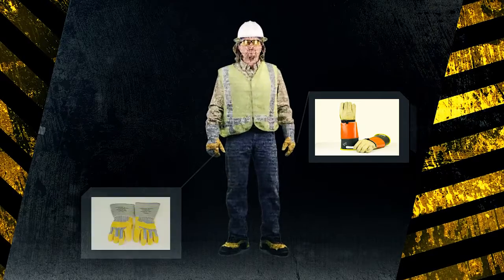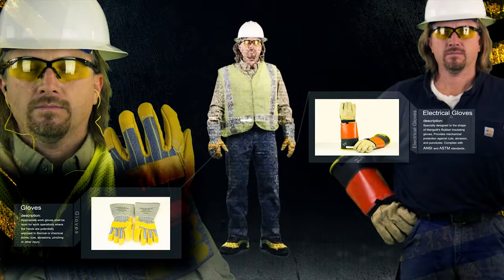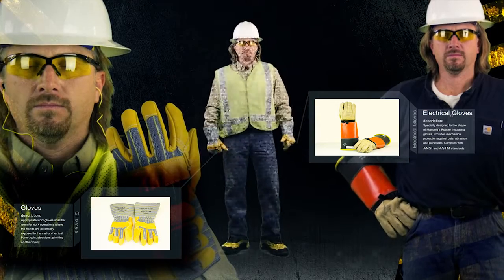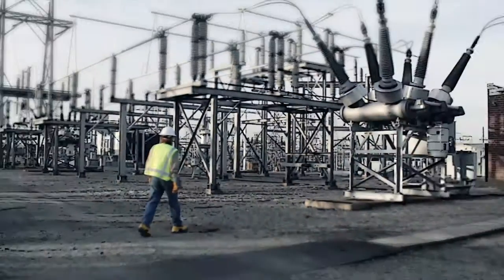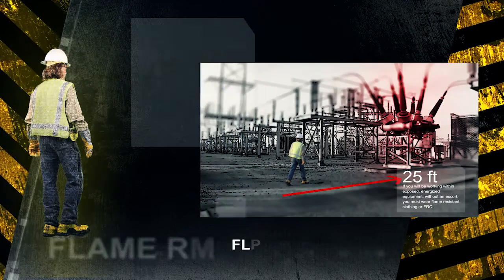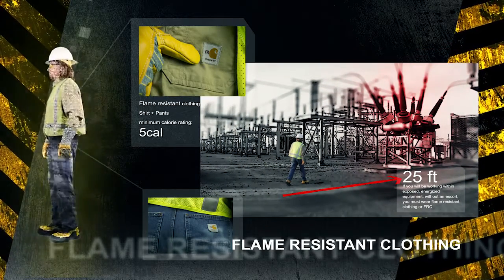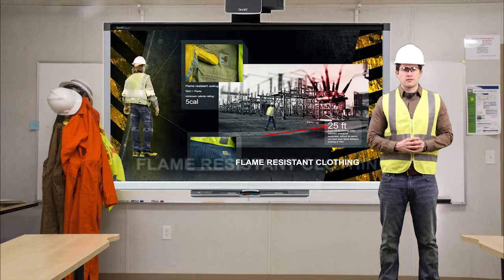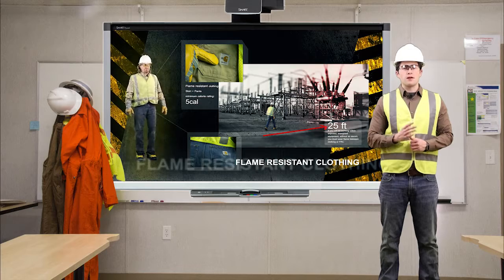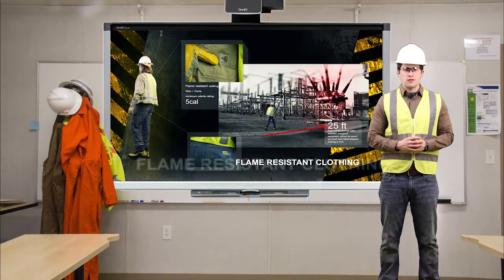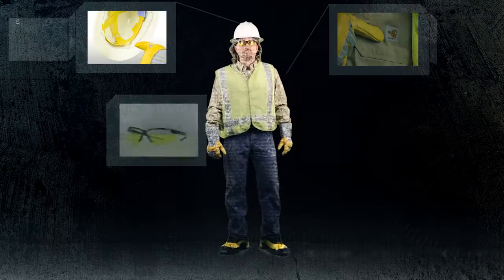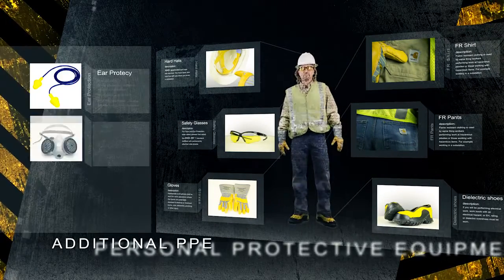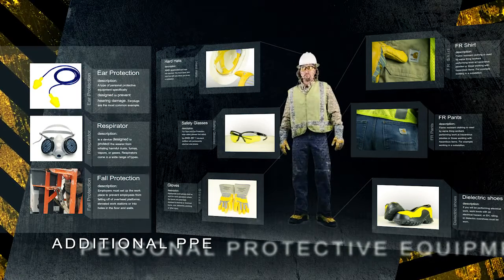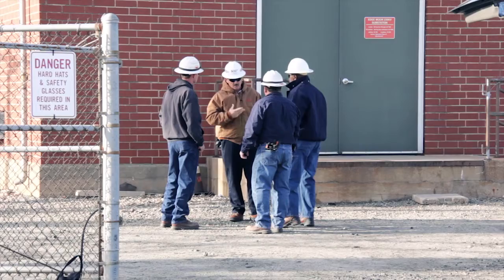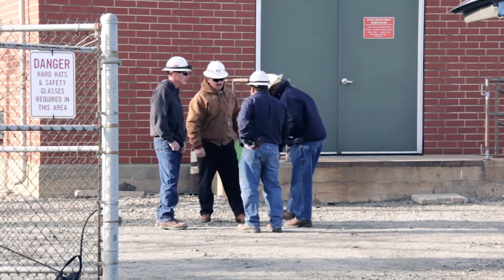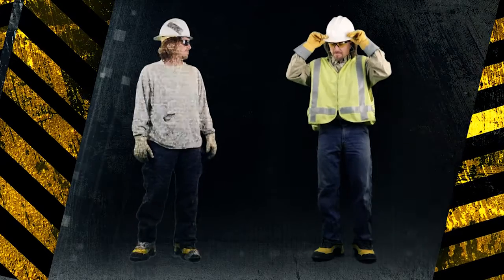Appropriate work gloves shall be worn for operations where the hands are potentially exposed to thermal or chemical burns, cuts, abrasions, pinching, or other injury. If you will be working within 25 feet of exposed, energized equipment without an escort, you must wear flame-resistant clothing, or FRC. All FRC must have a minimum rating of 5 calories. Additional PPE may be required based on the type of work being performed, including hearing protection, respirators, and fall protection. Required PPE should be discussed and identified during the tailgate session. All PPE should be in good condition.